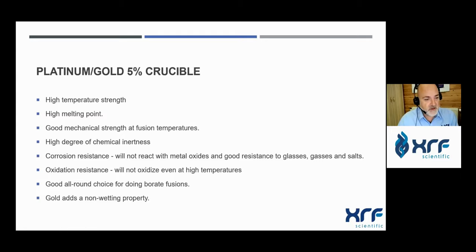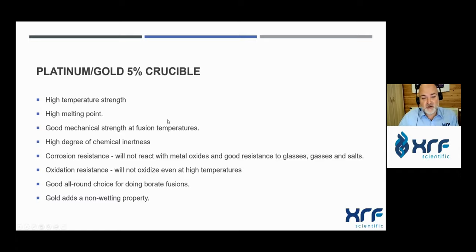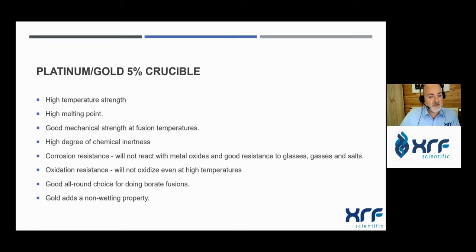Platinum-gold crucibles are used for borate fusion because they resist temperatures up to 1400°C, have good mechanical strength at high temperatures, are chemically inert, corrosion resistant, and oxidation resistant — making them the perfect crucible for borate fusion. It is important that all samples are fully oxidized before fusion, because metallics or sulfides can damage the platinum-gold crucible, just as in XRF fusion.